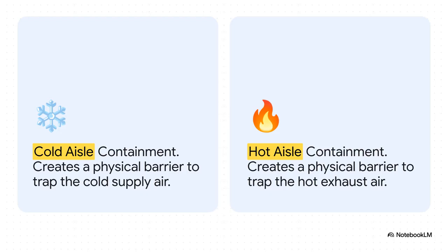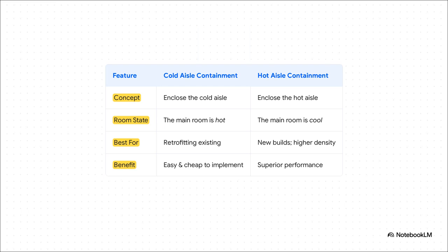This brings us to the two main strategies used today: cold aisle containment and hot aisle containment. The goal for both is the same, create a physical barrier using panels, doors, even little roofs, to stop the hot and cold air from ever mixing. With cold aisle containment, you build a box around the cold aisle. This is super popular for upgrading older data centers because it's cheap and easy, but the catch is the rest of the room becomes one giant hot zone.